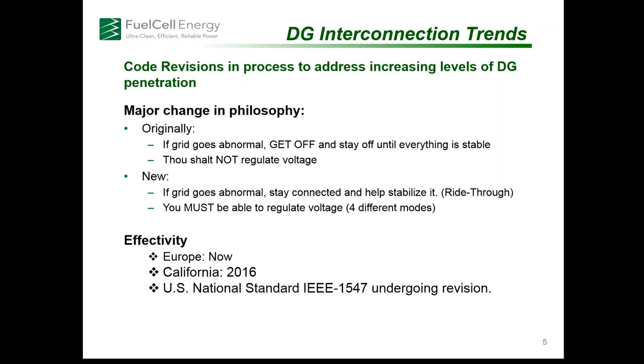In California, they have so much distributed generation that if it all took itself offline during some bulk system transient, it would be the equivalent of losing one or two nuclear units, making the problem even worse. So with new generation starting in 2016, they want distributed generators to stay connected and help recover the system, feeding power into it instead of dropping off.